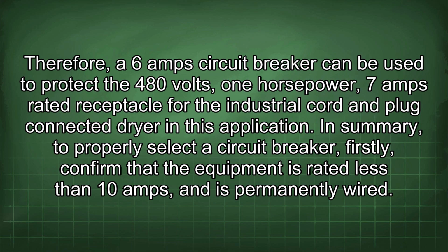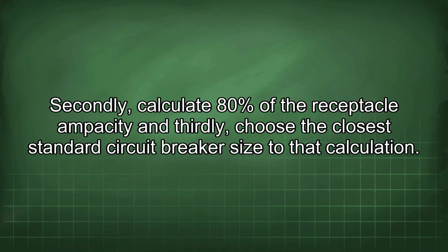In summary, to properly select a circuit breaker, firstly confirm that the equipment is rated less than 10 amps and is permanently wired. Secondly, calculate 80% of the receptacle ampacity, and thirdly, choose the closest standard circuit breaker size to that calculation.